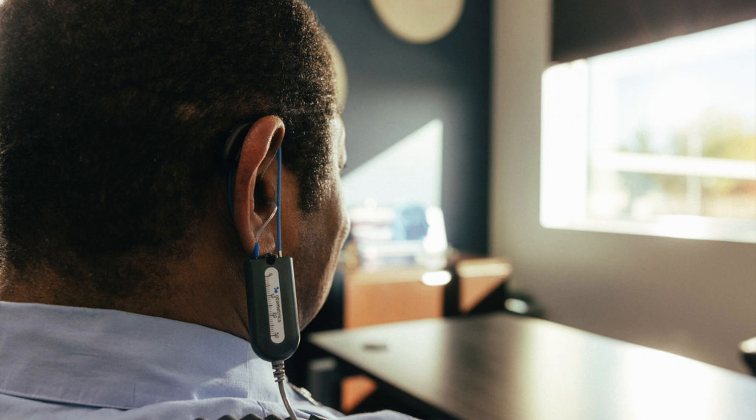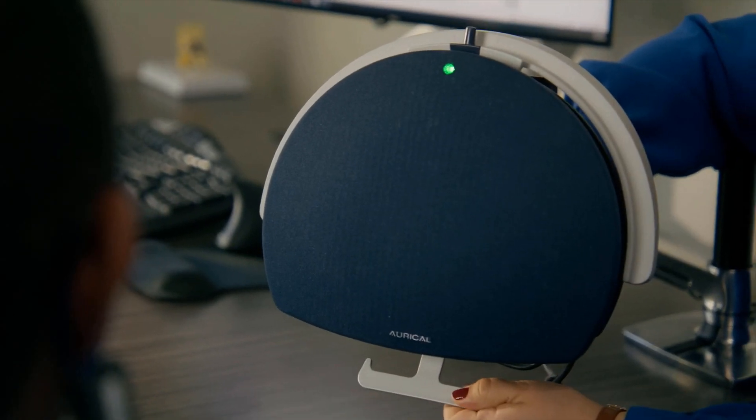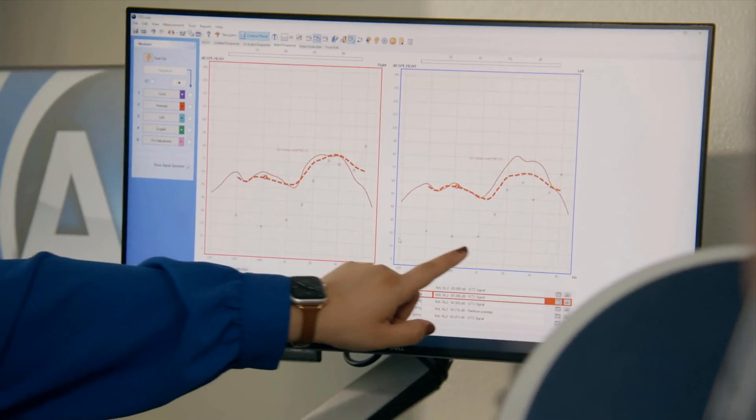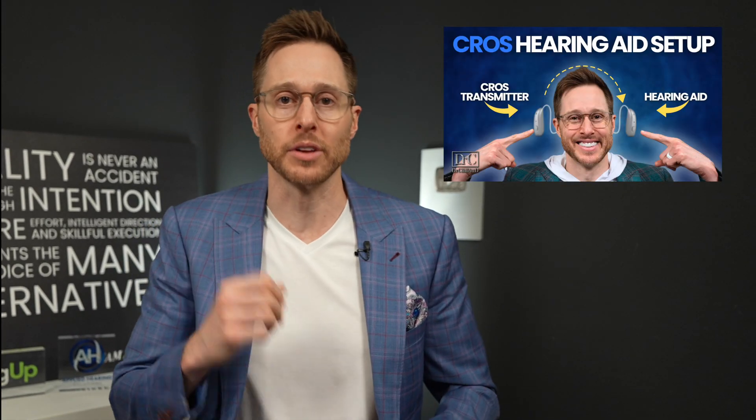Something that is extremely important when it comes to having success with CROS treatment is real ear measurement. Real ear measurement is a way for your hearing care professional to verify that the amount of sound being transmitted from your CROS side to your hearing aid side is actually overcoming the head shadow effect as well as meeting your hearing loss prescription on your better hearing ear. I am serious when I say this — it is quite literally impossible to correctly program your CROS transmitter to your hearing aid if you are not doing real ear measurement to verify this fitting. If you would like to learn more about verifying a CROS fitting, I will have this video linked down in the description.